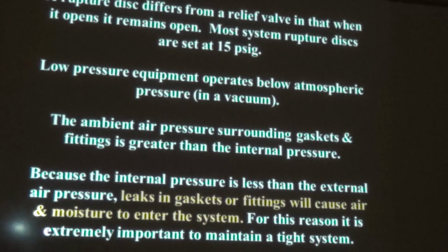Because the internal pressure is less than the external air pressure, leaks in gaskets or fittings will cause air and moisture to enter the system. For this reason, it's important to have a tight system, and it's going to be also important to have a purge system.